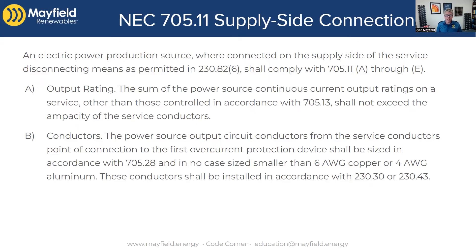A lot of times supply side connections are done on commercial or larger systems, but there are cases where you do a supply side connection on a residential application. So having this rule — knowing you need 6 AWG copper from the point of connection to the first overcurrent device, regardless of size — is helpful. In reality, even if it's a small system with only a 30 or 40 amp overcurrent device, yes you're oversizing wires, but it's a short run, so it's not a huge cost implication. We're going to look at that here in a minute.